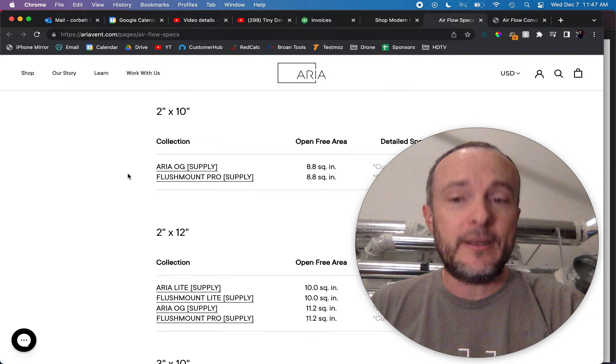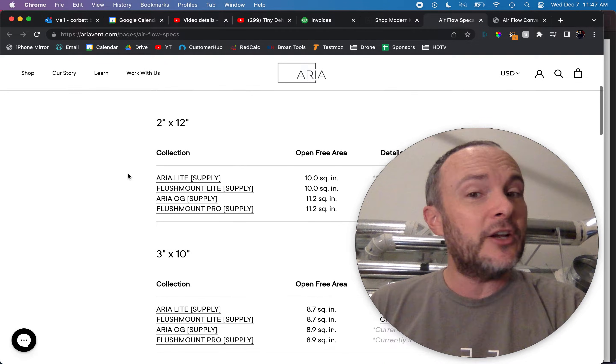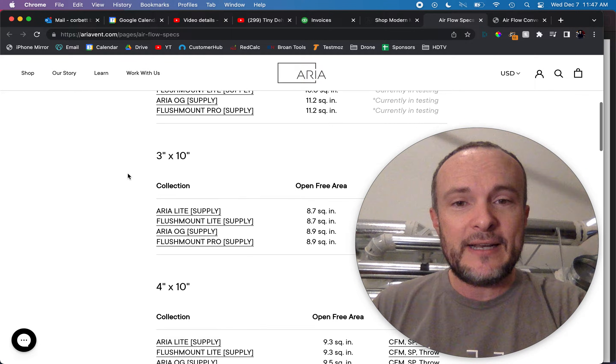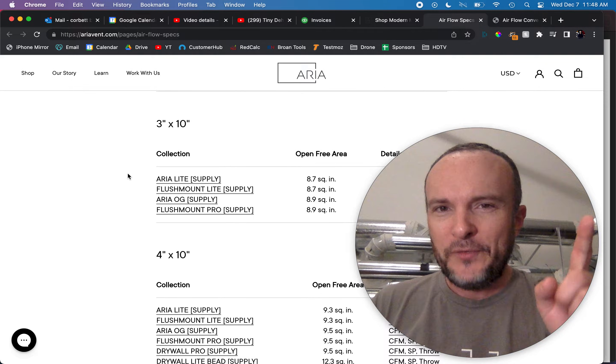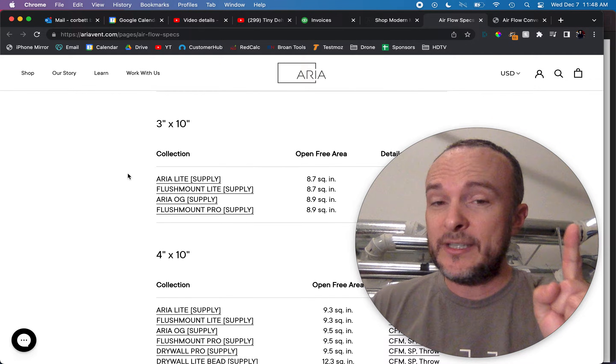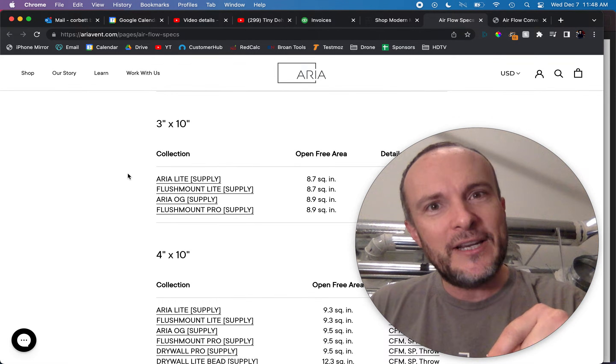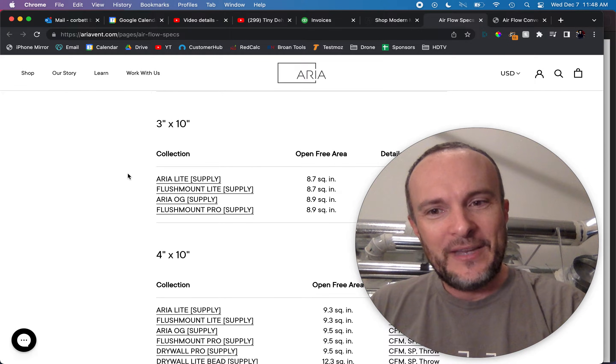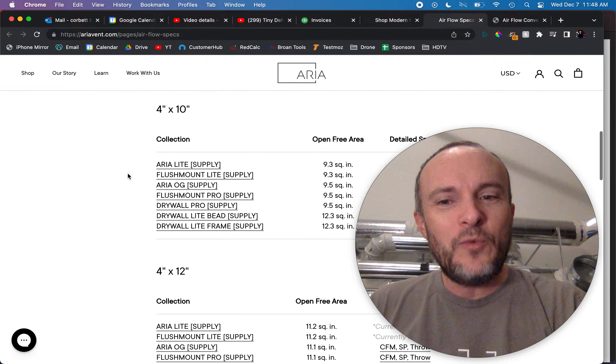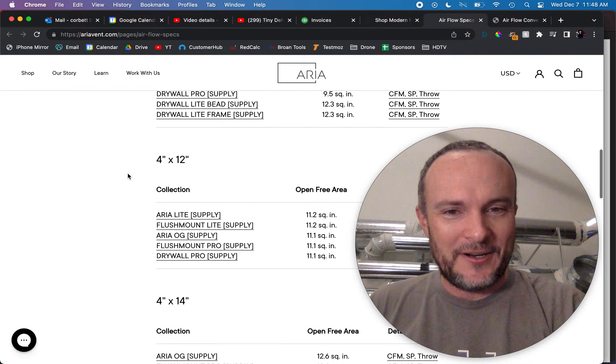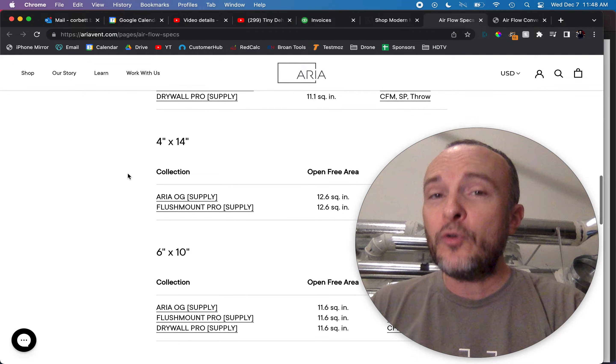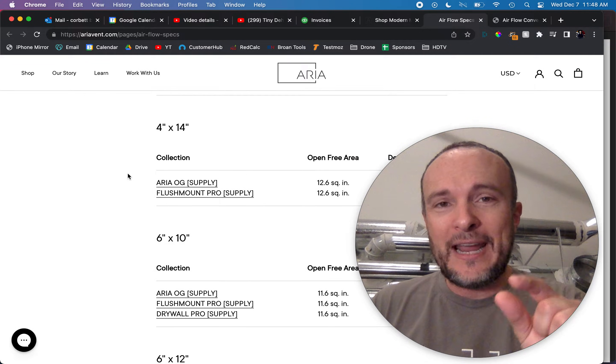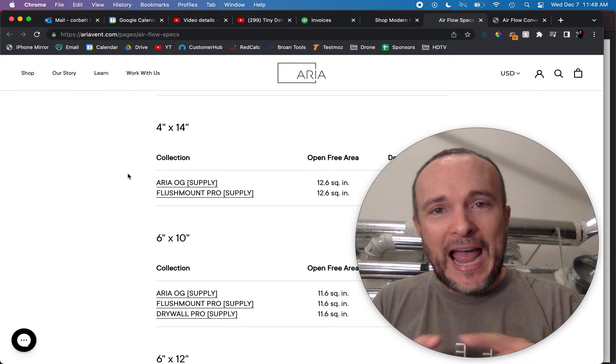That's a good starting place to talk about. 2 by 12 it goes up by a couple inches, that's great. But then you can see 3 by 10 which is actually 30 square inches, supposedly the number actually goes down. And as you can see when we go up in size here what happens is that the proportion of net free area to the size of the actual grill that you're buying is going down and down and down.